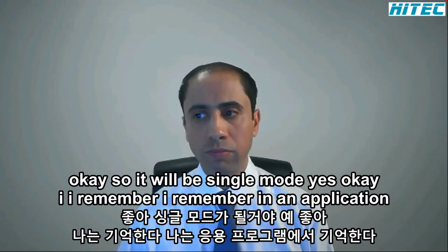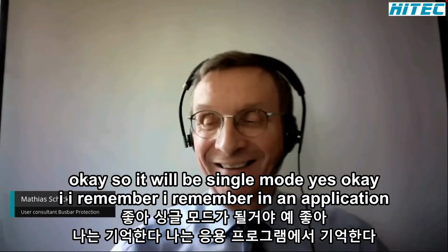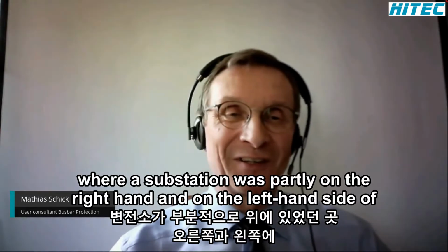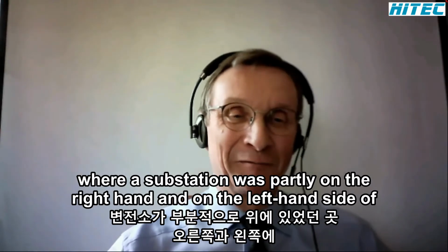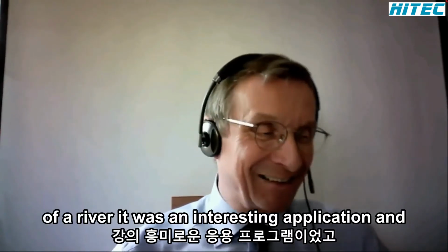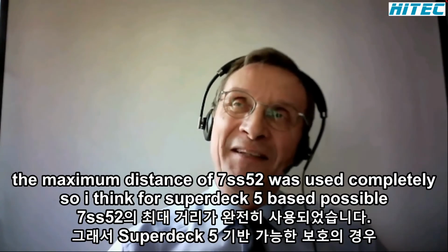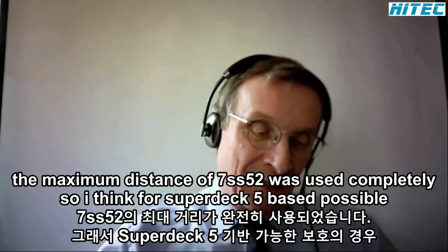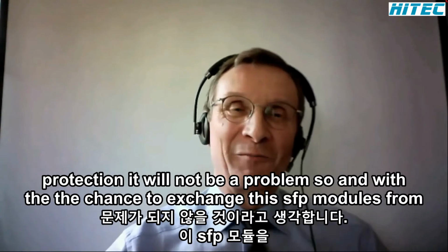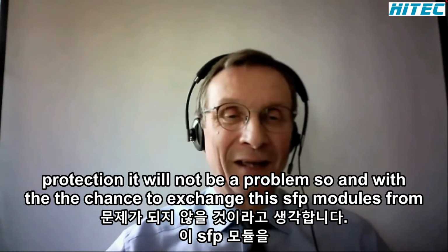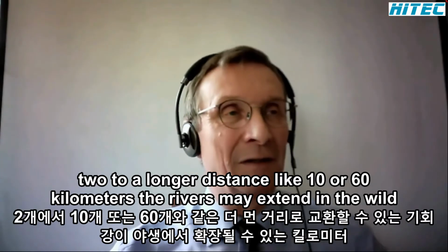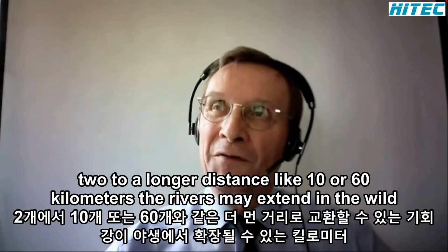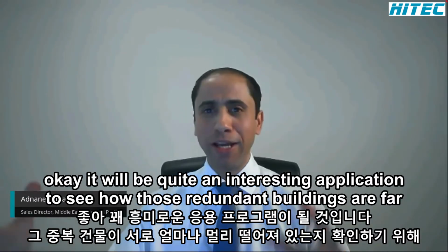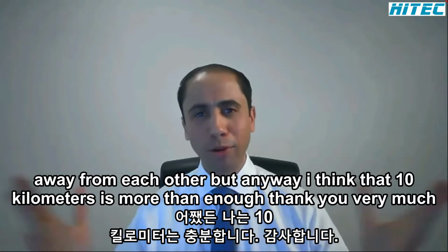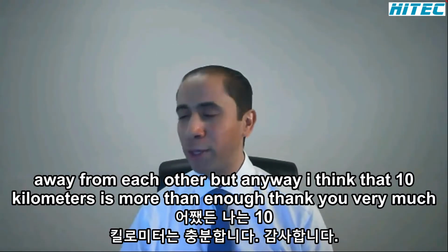Yes. I remember an application where a substation was partly on the right hand and on the left hand side of a river. It was an interesting application, and the maximum distance of the 7SS52 was used completely. So I think for a SIPROTEC 5 based busbar protection, it will not be a problem. With the chance to exchange these SFP modules from 2 kilometers to longer distances, like 10 or 60 kilometers, the rivers may extend in their width. Okay, it will be quite an interesting application to see how far away from each other those redundant buildings are. But anyway, I think that 10 kilometers is more than enough. Thank you very much, Matthias.